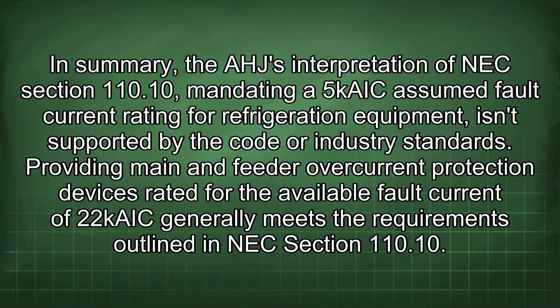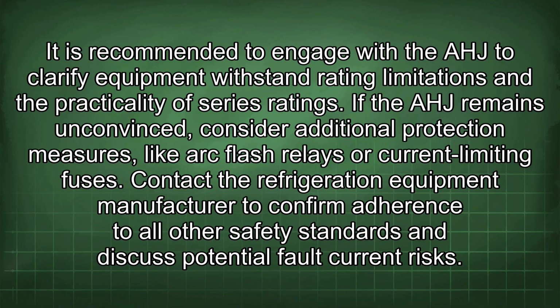Providing main and feeder overcurrent protection devices rated for the available fault current of 22kAIC generally meets the requirements outlined in NEC Section 110.10. It is recommended to engage with the AHJ to clarify equipment withstand rating limitations and the practicality of series ratings. If the AHJ remains unconvinced, consider additional protection measures like arc flash relays or current limiting fuses. Contact the refrigeration equipment manufacturer to confirm adherence to all other safety standards and discuss potential fault current risks.